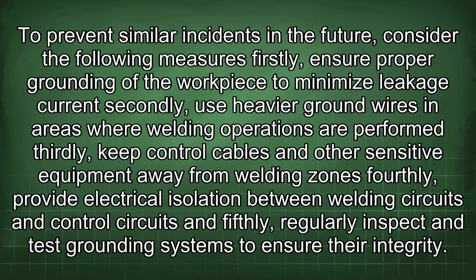Firstly, ensure proper grounding of the workpiece to minimize leakage current. Secondly, use heavy ground wires in areas where welding operations are performed. Thirdly, keep control cables and other sensitive equipment away from welding zones. Fourthly, provide electrical isolation between welding circuits and control circuits. And fifthly, regularly inspect and test grounding systems to ensure their integrity.